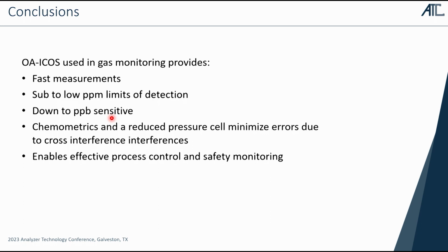And we can go to these levels because we're combining multiple factors: a very, very long path length, kilometers, very low pressure, nice sharp peaks, and chemometrics to help account for any remaining overlap. You will never remove all the overlap in some of these things. You have to account for it, so you regress about it with a chemometric technique. Operating outside of its calibration range, we'll do that. It won't be as accurate. You have to question the absolute value of the number, but the trend is real due to the sensitivity.